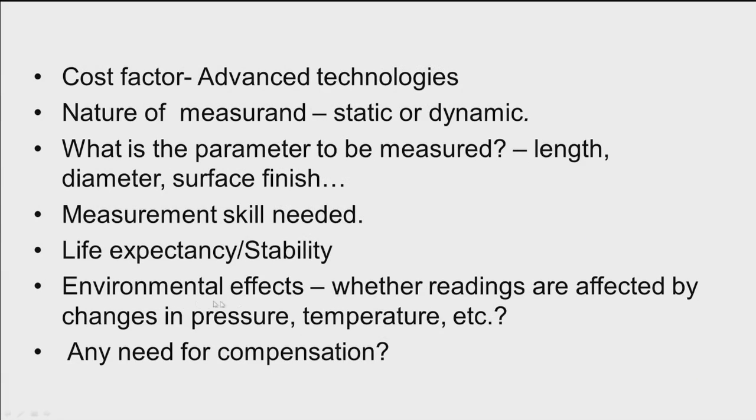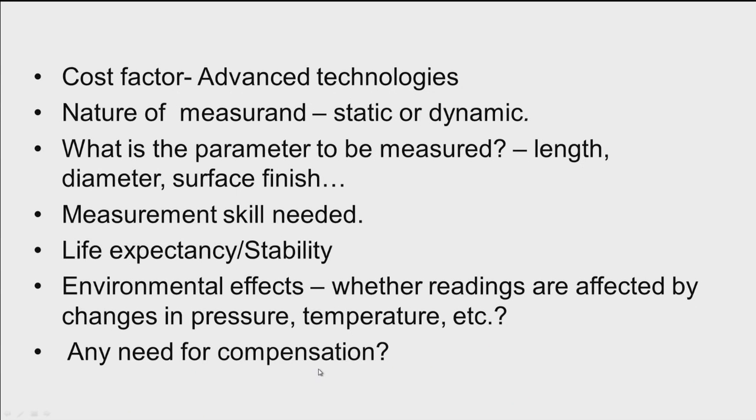Environmental effects must be considered — whether readings are affected by changes in pressure, temperature, etc. If there is deviation from standard temperature, we need to know the amount of change in dimension due to temperature change and compensate accordingly, or calibrate the instruments at the particular temperature where measurements are taken.